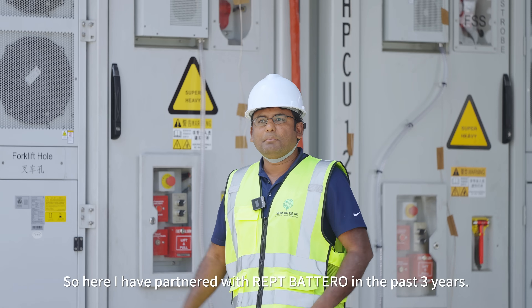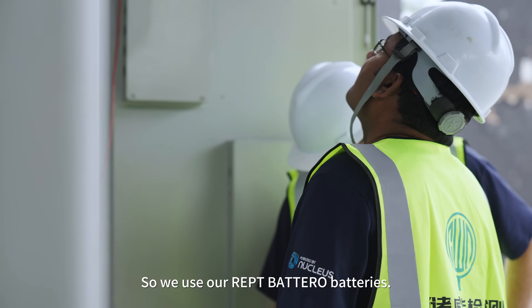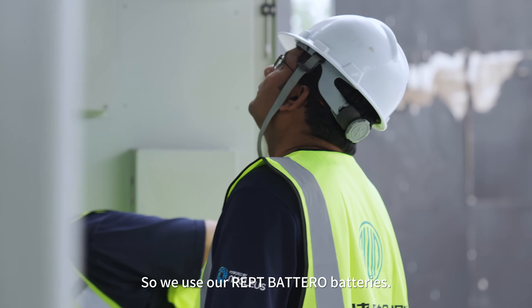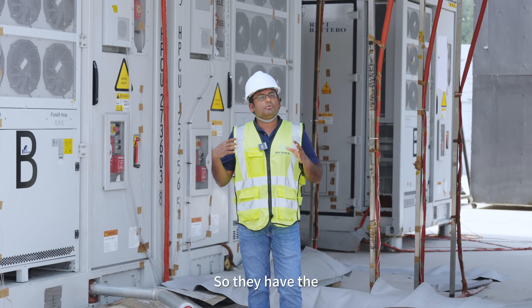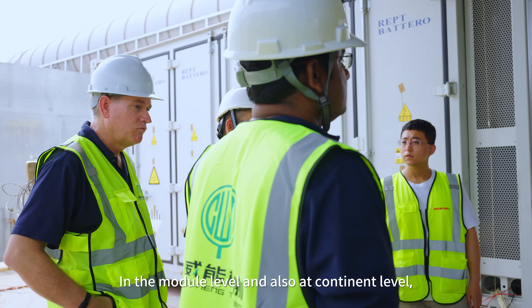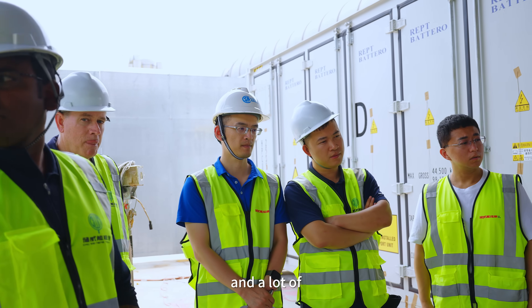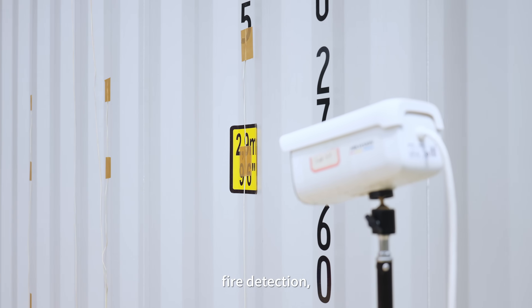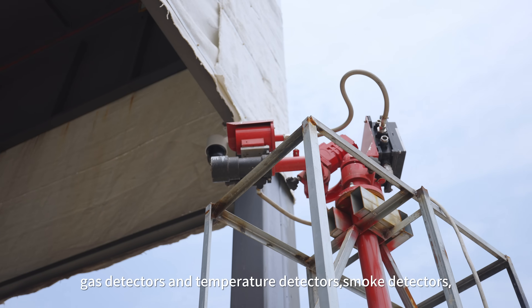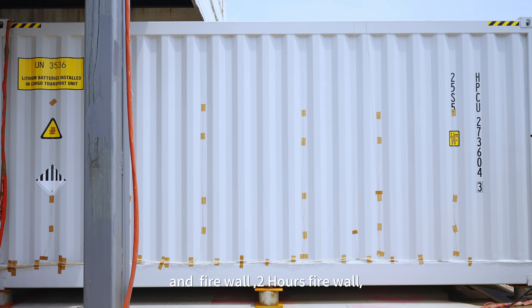We have partnered with REPT BATTERO for the past three years, so we use their batteries. Our batteries are designed very well — they have a fire suppressing system built in at the module level and also at the container level, along with fire detection, gas detectors, heat detectors, smoke detectors, and a two-hour firewall. It's a pretty good product.